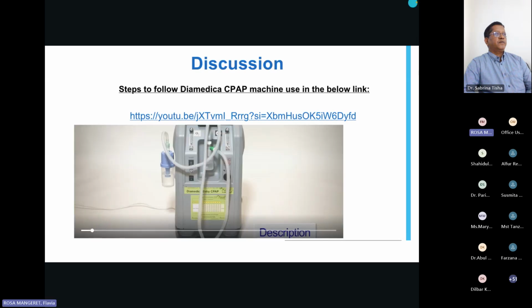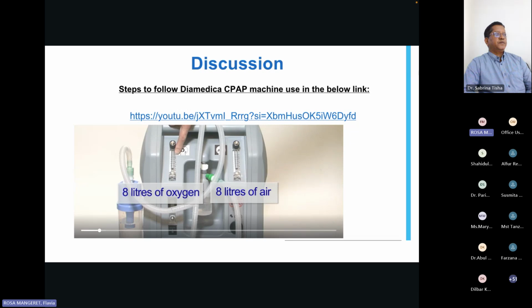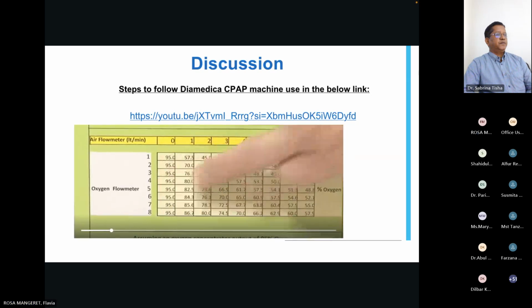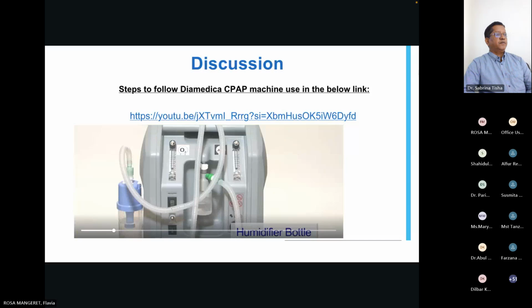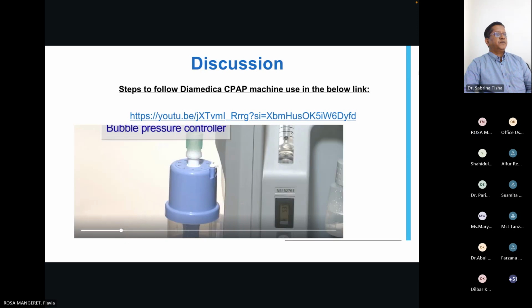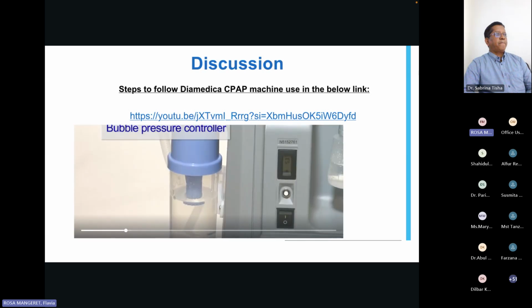CPAP is a unique design providing high flows of oxygen and air from atmosphere using a modified oxygen concentrator. Up to 8 litres per minute of oxygen and 8 litres of air are controlled by separate flow meters, allowing a variable gas mixture to the patient containing oxygen from 21% to 95% calculated by this chart. The gas mixture is humidified by this bottle before being delivered to the patient through silicone nasal cannula. The CPAP pressure is controlled by a bubble device on the side of the concentrator.